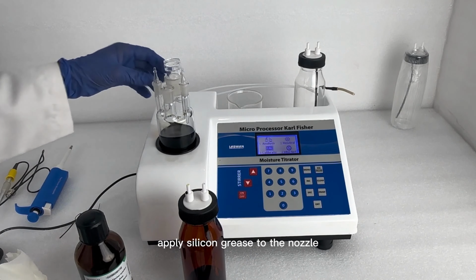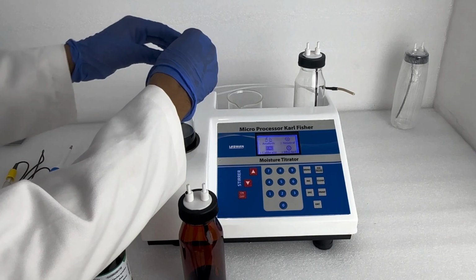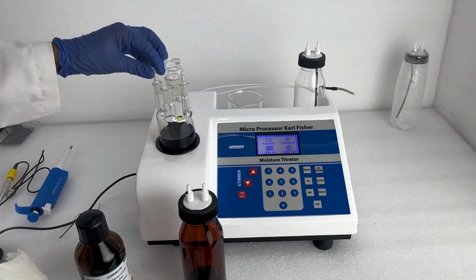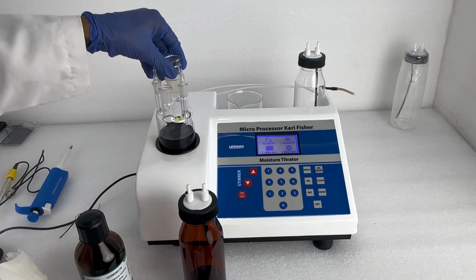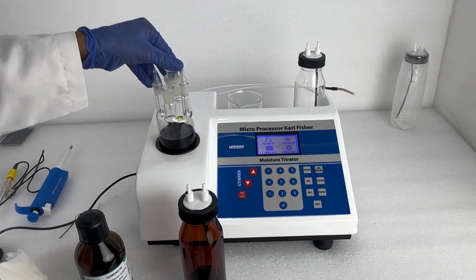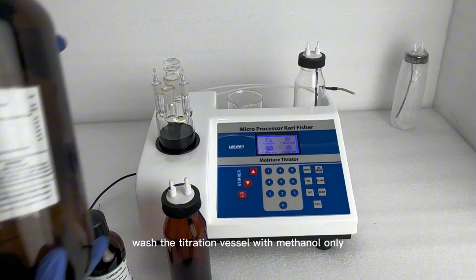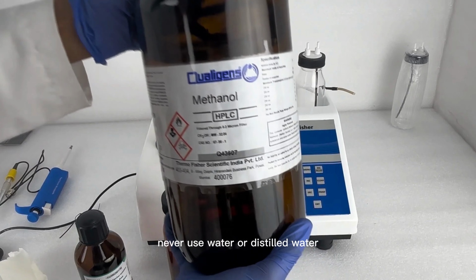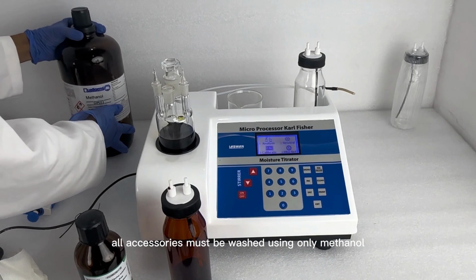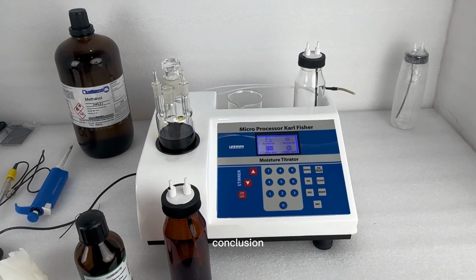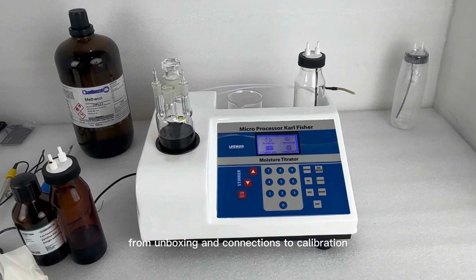Apply silicone grease to the nozzle after cleaning to prevent sticking. Wash the titration vessel with methanol only. Never use water or distilled water. All accessories must be washed using only methanol. Conclusion. That completes the entire Karl Fischer setup and operation process, from unboxing and connections to calibration, analysis, and cleaning. There are also other advanced methods not shown in this video that you can explore as per your requirement. Thanks for watching.